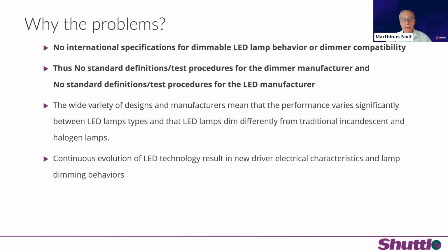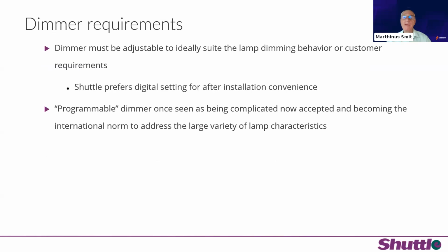Now, unfortunately, because of that continuous evolution in LED technology, the number of manufacturers, as well as the lack of specifications, your dimmer actually has to evolve dynamically with your lamp. So your ideal dimmer requirement is that your dimmer must be adjustable to ideally suit all your lamp behaviors. And that is also a very dynamic thing. It changes the whole time. We prefer digital settings because they can be done after installation very easily, and it's easy to assist the end client to do settings if required.